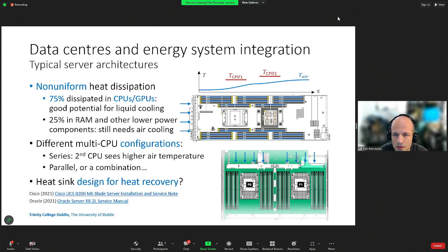Most of the heat is dissipated in the CPUs or GPUs, and the RAM represents about a quarter of the total heat dissipation. So the challenge here is that it's quite a non-uniform heat distribution. The CPUs are quite small, and they represent about three quarters of the heat dissipation. The memory modules are more distributed, so air cooling is probably more appropriate for them, and liquid cooling is typically seen as more appropriate for CPUs, perhaps.